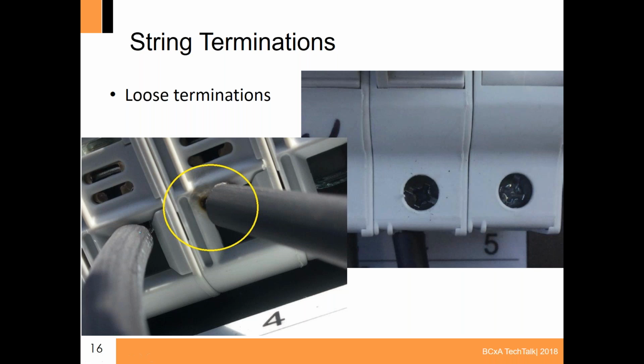So again, one of the things we look for is verifying that electrical connections are absolutely perfect. They're a common point of failure. So we want to make sure, again, through thermal imaging and through torque verification, that they are made up properly.